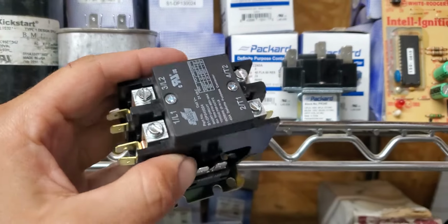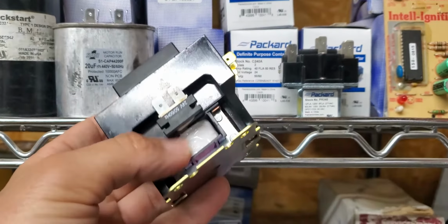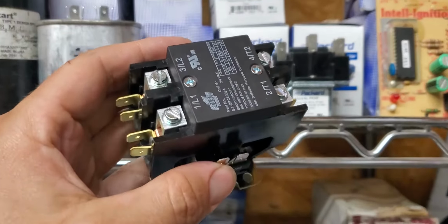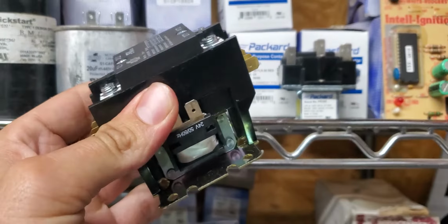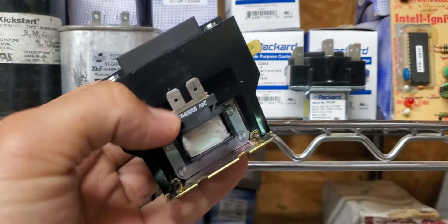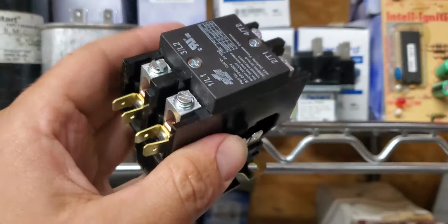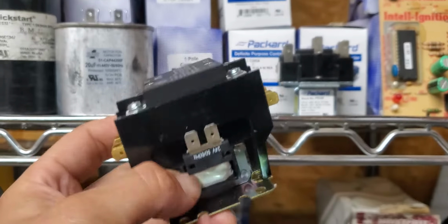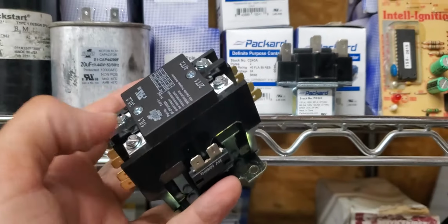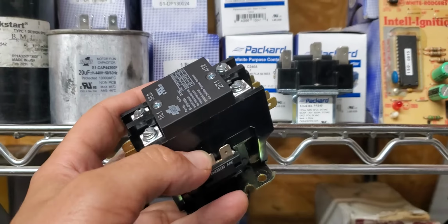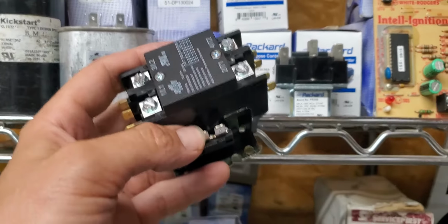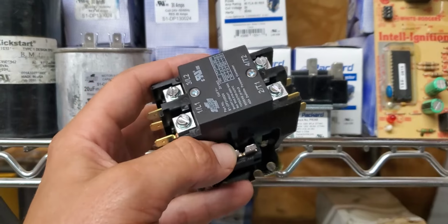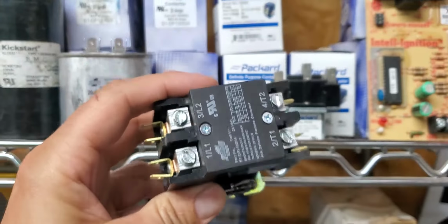You can also have a contactor that gets shorted on the coil, so it blows a fuse every time. Well, if you have a fuse blow, it could be the contactor. So you isolate this, put your fuse back in, and see if it works, but those are common issues with this. Also, it can stay closed because of carbon buildup. So you'll have your fan and compressor running constantly. You're like, what's going on? My fan's not even blowing, my system's off, but my unit's running.